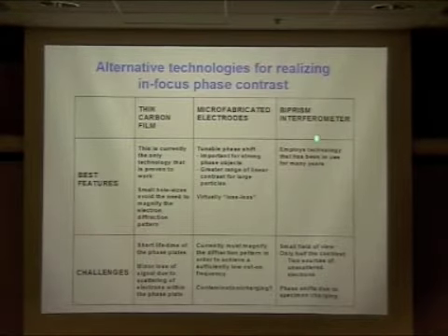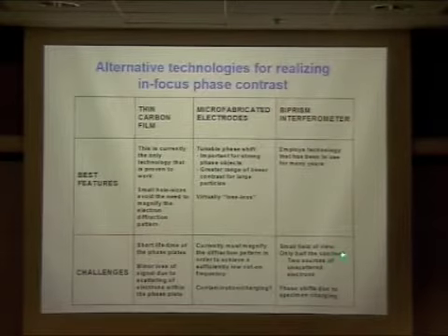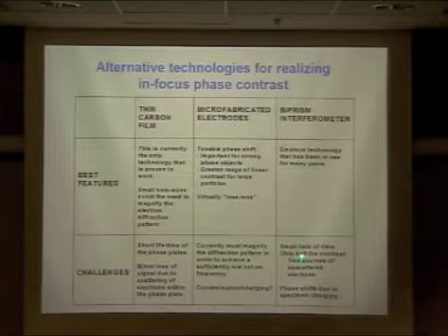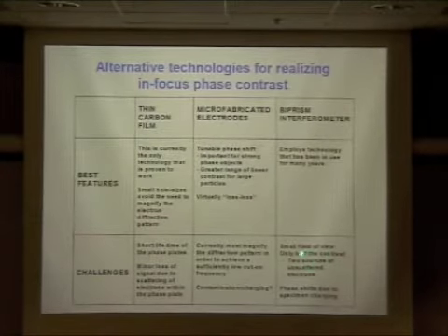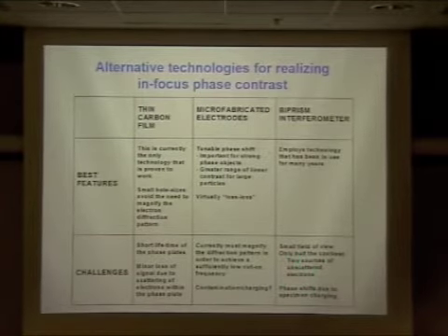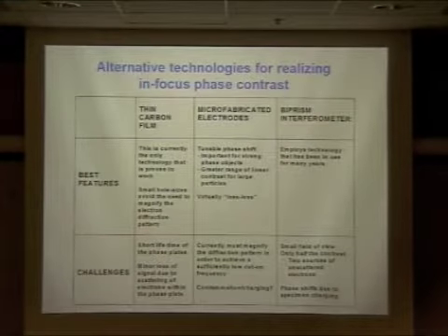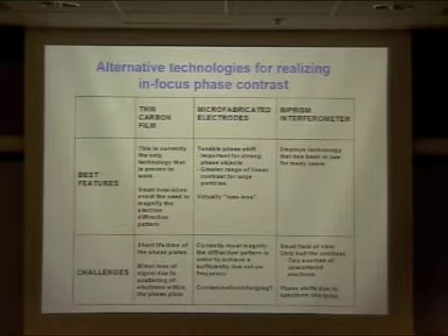The biprism interferometer has a disadvantage that it produces fringes or interference effects in the image that are equivalent to phase contrast over only a very small field of view. You have two sources of unscattered electrons: the unscattered electrons that flow through the specimen and the unscattered electrons that flow through the reference field, and they're both superimposed.